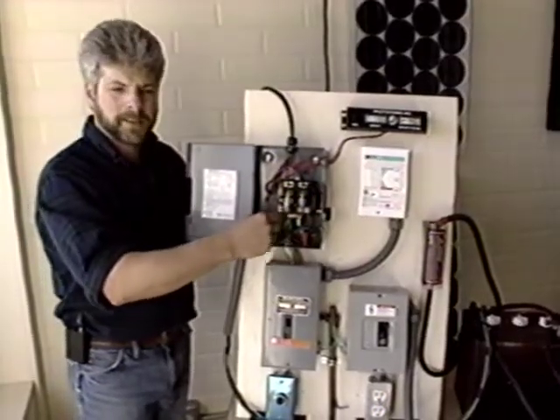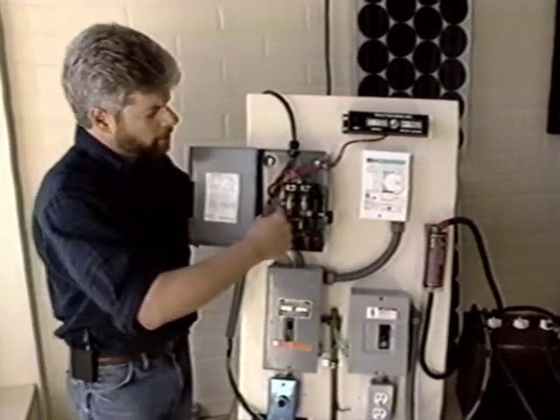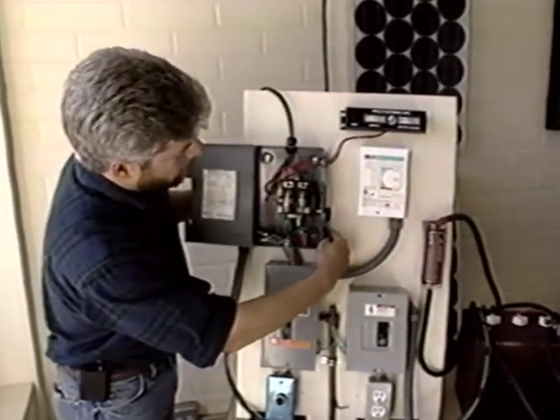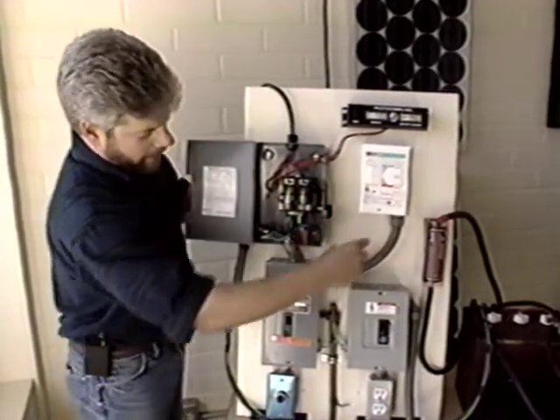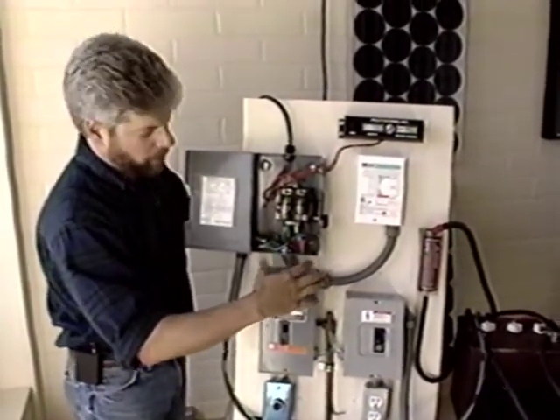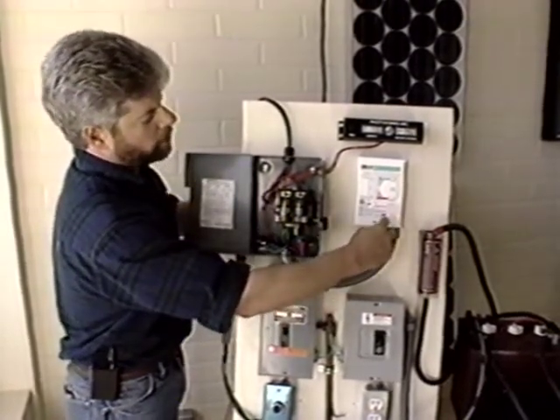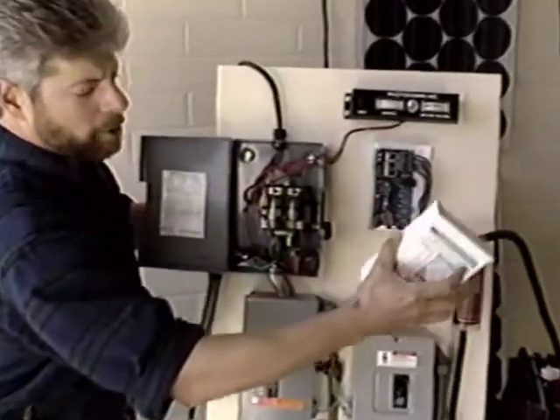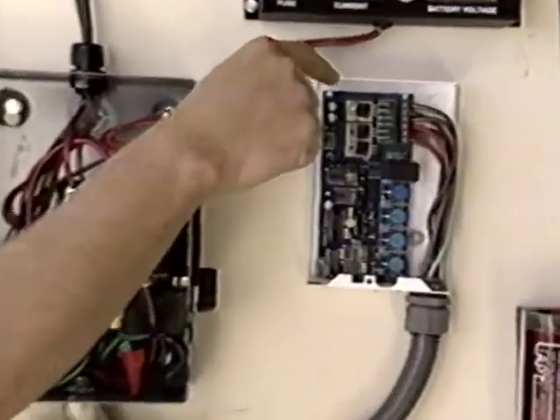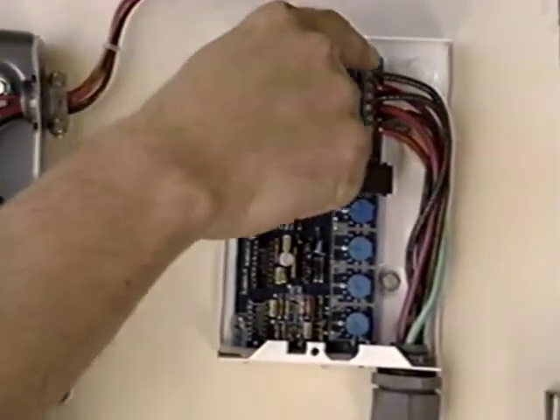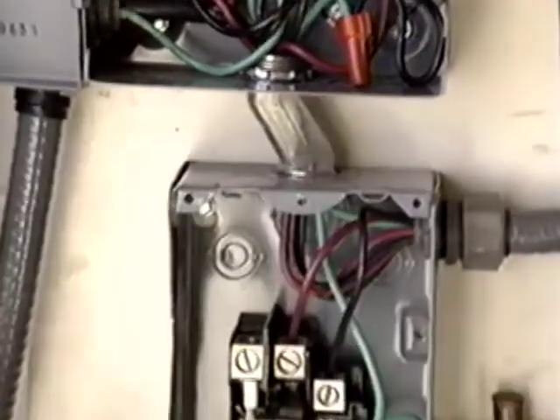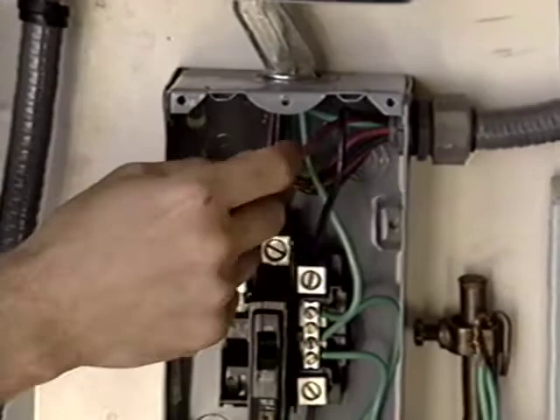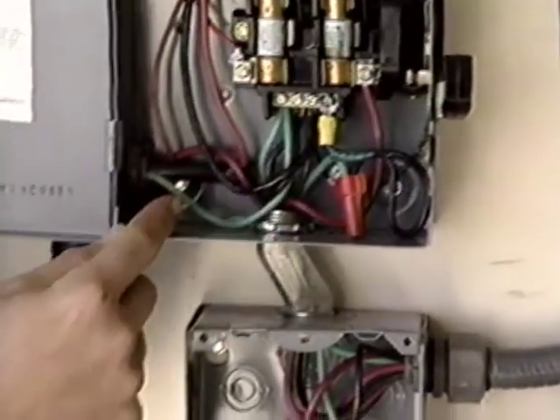Once the array power is disconnected and fused, the wires go over to the charge controller. They get to the charge controller by going through this box here, which we'll see in a minute. But the wires go up to the charge controller, and then the charge controller can do its job of regulating array power. The power comes back out and goes into the DC load center, back up here, and then over to the battery for array charging of battery.